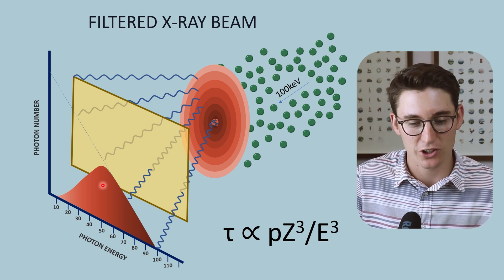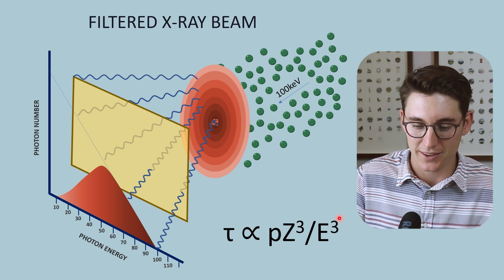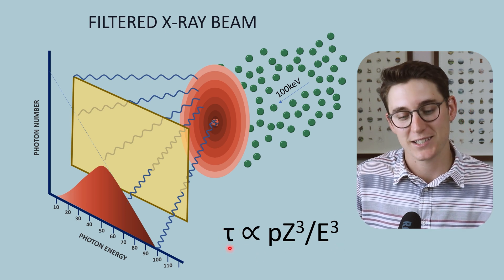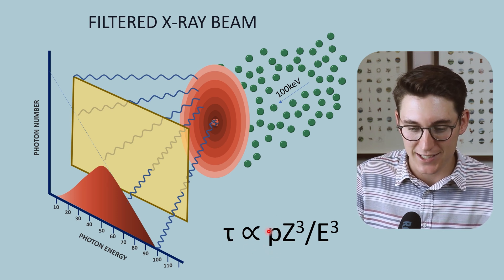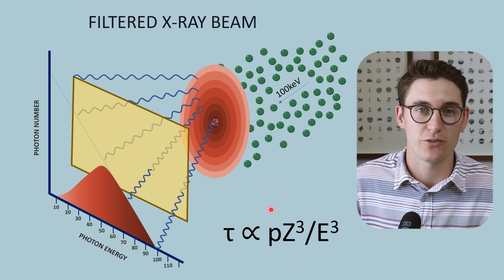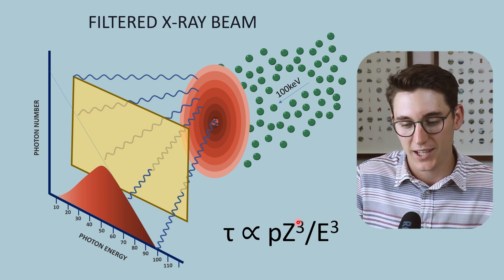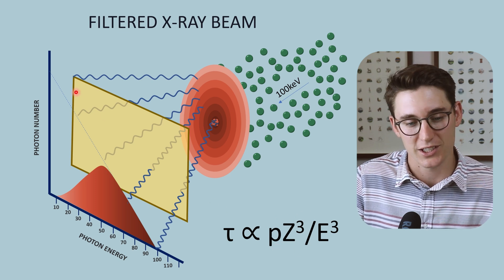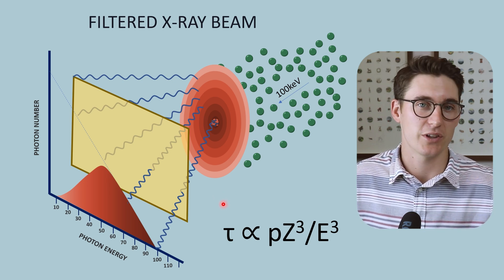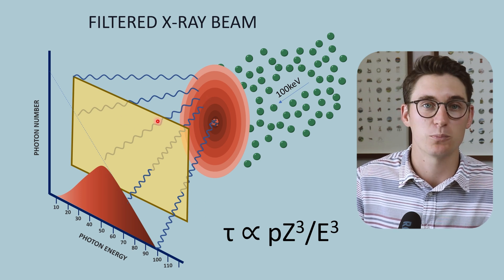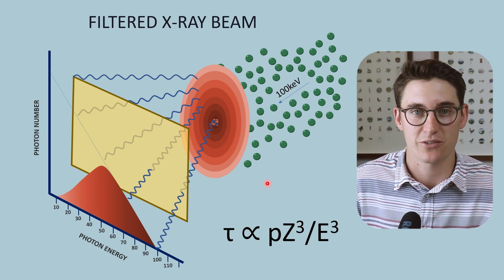Filtration occurs by an effect called the photoelectric effect. The photoelectric effect is defined by this function, where tau (τ) represents the likelihood of the photoelectric effect to occur. If we increase the density of our filter, we increase the likelihood of the photoelectric effect and the likelihood of x-rays being attenuated. If we increase the atomic number of our filter — we often use aluminium with atomic number 13, but tungsten has atomic number 74 — we get much more attenuation, because atomic number cubed is proportional to the likelihood of the photoelectric effect.